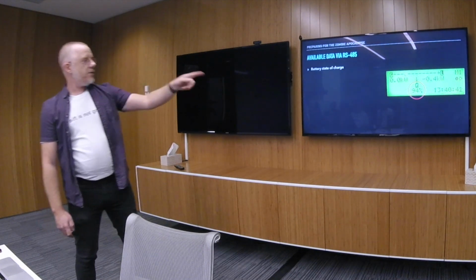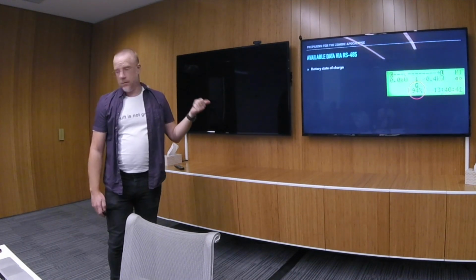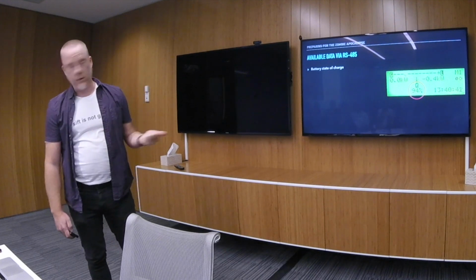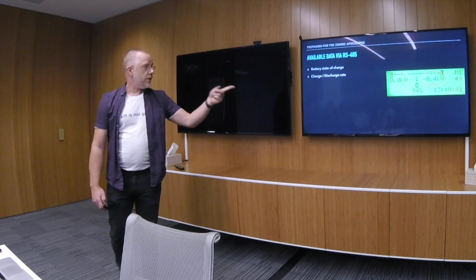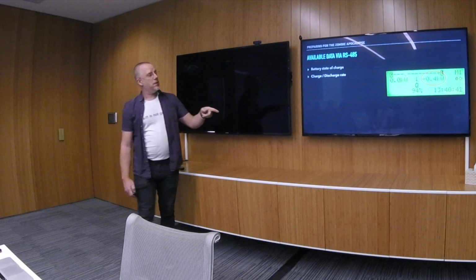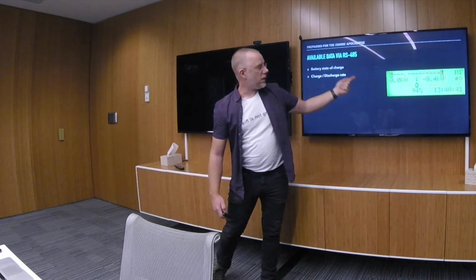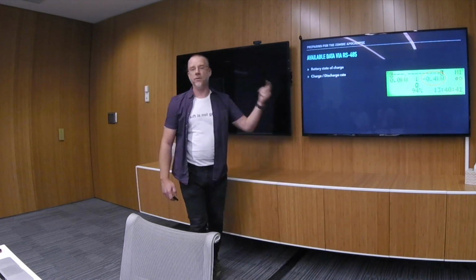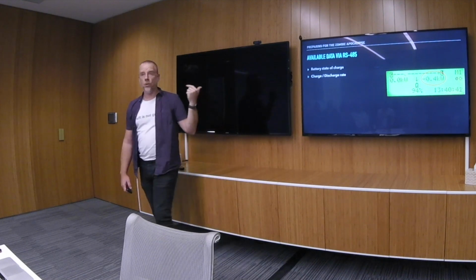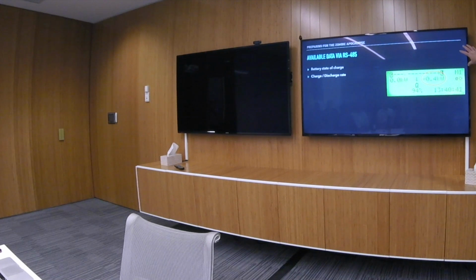So these are the key pieces of information I can get via RS485: the state of charge, the charge and/or discharge rate. The arrow is pointing to the loads, and a negative 0.4 kilowatt load means the battery's charging 0.4 kilowatts. In this diagram, the solar panels are over here, so what this is telling me is the power's going that way, into the battery.